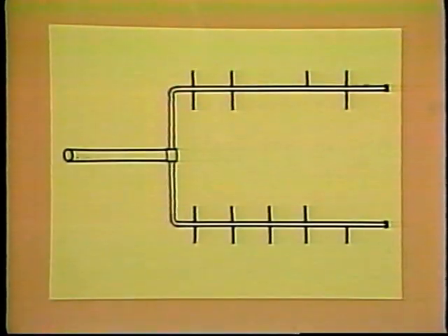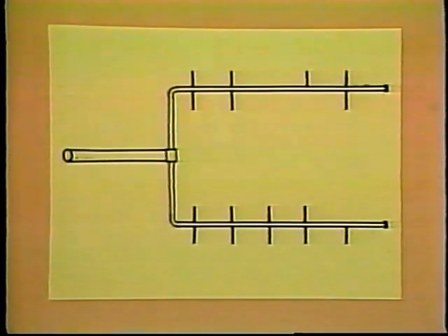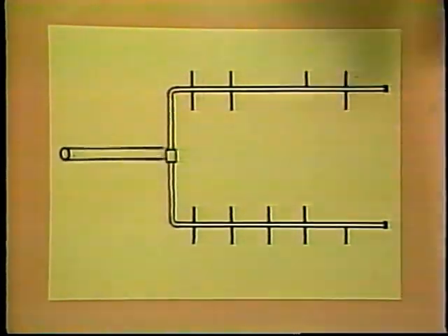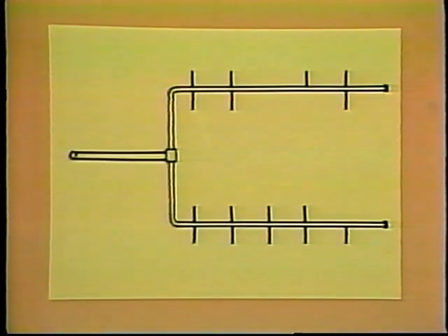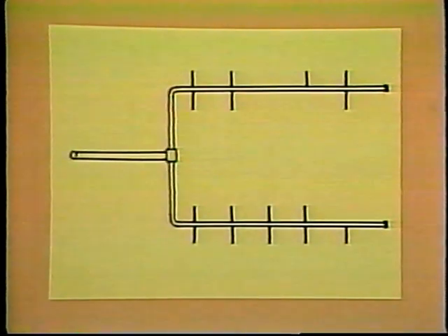Let's say we have a system requiring 520 SCFM of air, and through one pipe, it will move with a velocity of 100 feet per second. Through a smaller pipe, with say 1/2 the cross-sectional area, we can still get 520 SCFM. But now the air must travel twice as fast, or 200 feet per second.